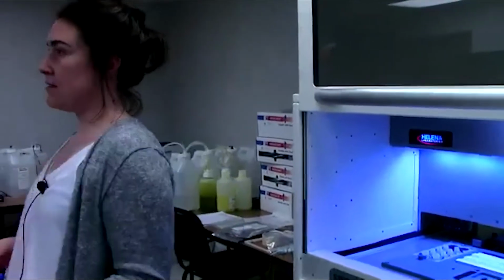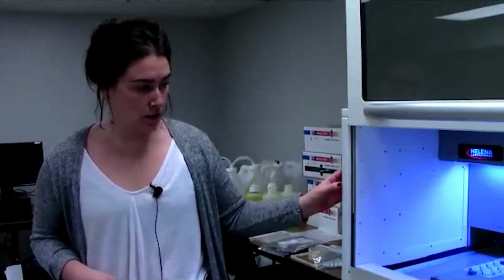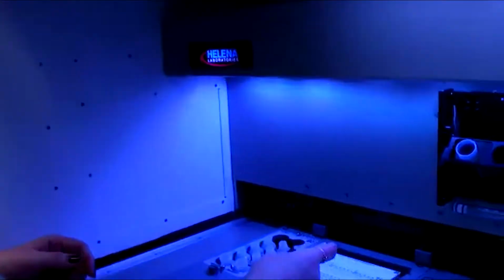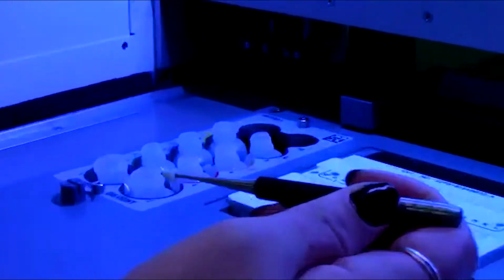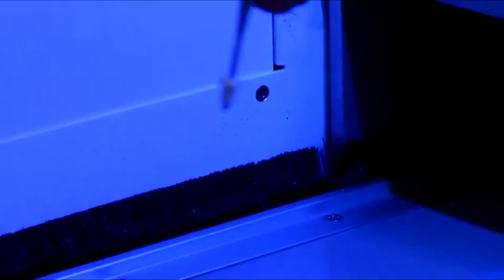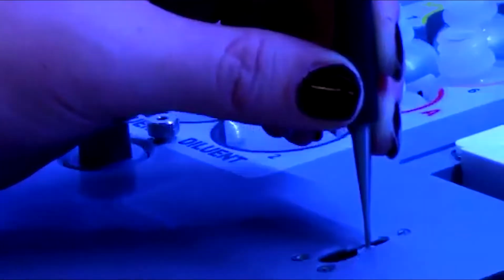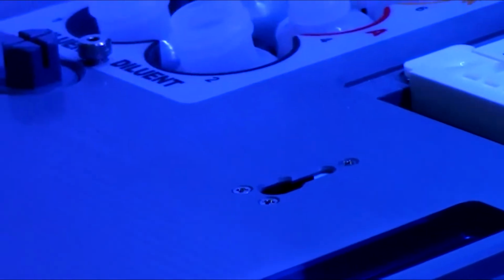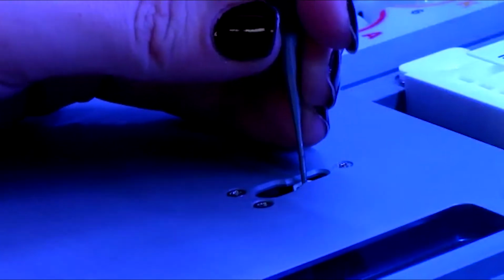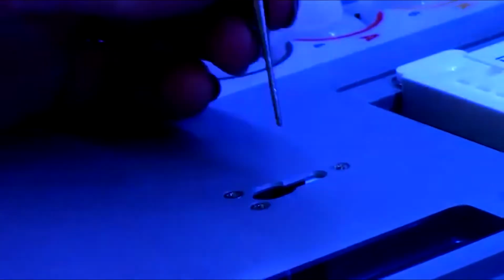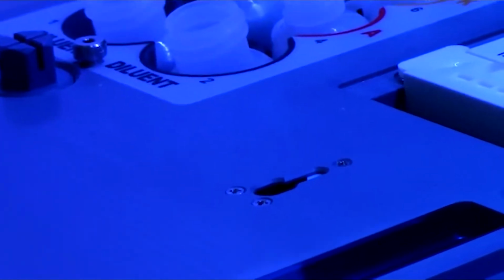Emily, can I just interrupt you for 1 second? Can you show them the orientation one more time of the spreader tip? Because I know that sometimes it's confusing whether it's right side up or upside down. Yeah, definitely. All right, so the spreader tip actually sits to where the broad side is at the top, and it keeps it from going too far down in. So the spreader tip sits in the shape of a T. The spreader tip slides back in, and that's where it'll sit. And you'll notice it'll snap into place. We have a clip there that makes it snap back into place, so it's always in the same position when the pipette comes to pick it up.